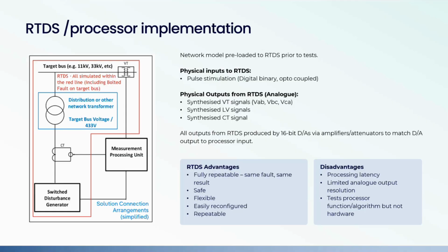The processor initiates disturbances as normal, and that physically stimulates the computer. Then the computer models the disturbance generation hardware to synthesize the pulses at LV. It models the coupling through the transformer to the target bus and the voltage response to them. Those digital responses are then fed to digital to analog converters to provide the physical response signals back again to be measured by the processor. So the processor has the same information as it has in a full system, and it computes the prospective fault level as normal.